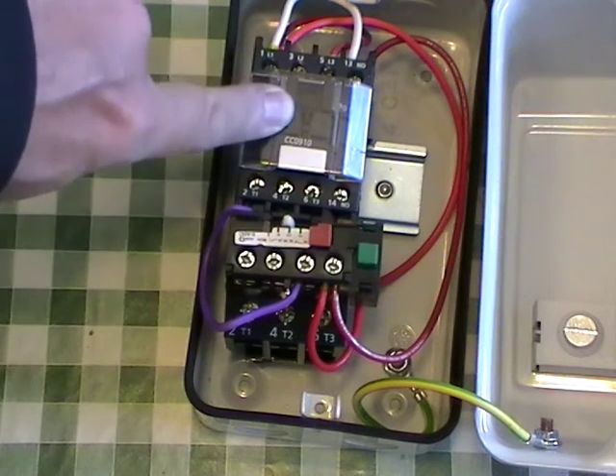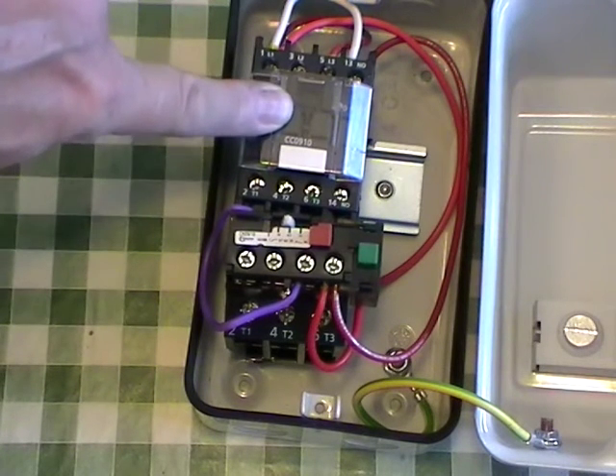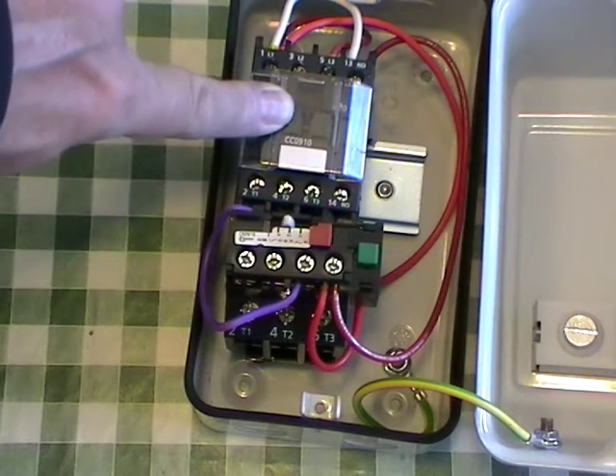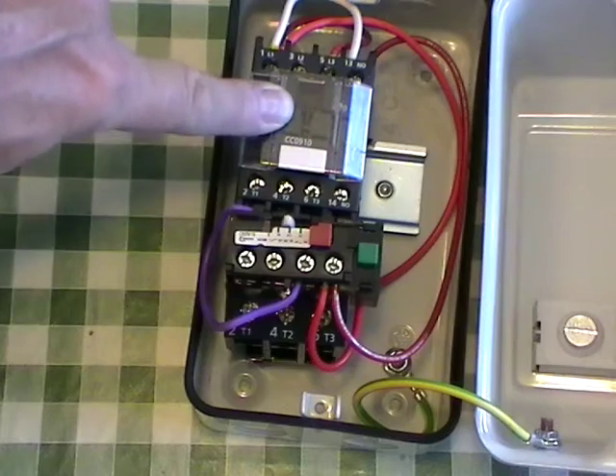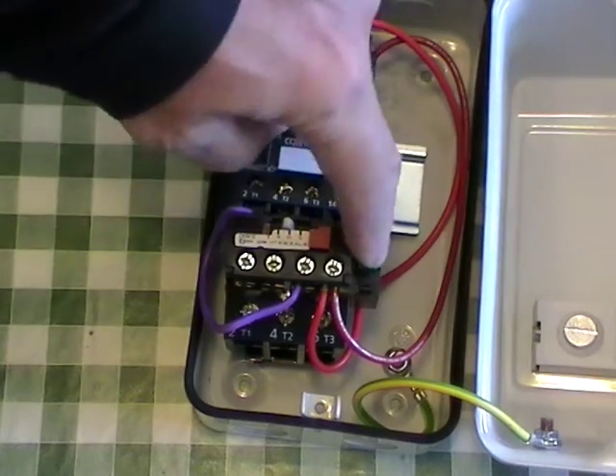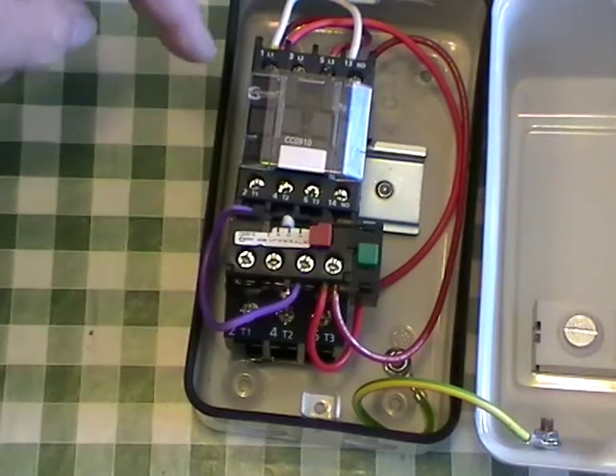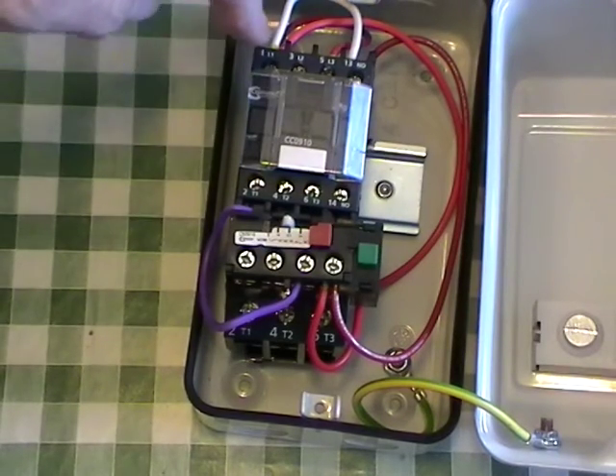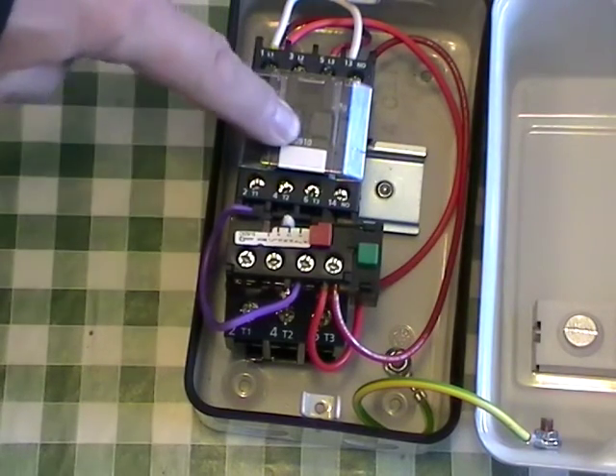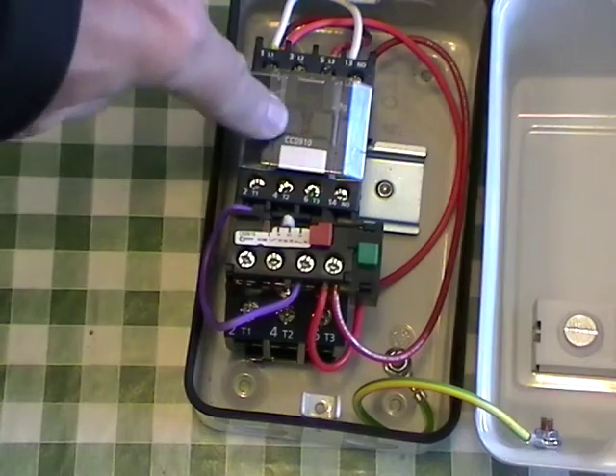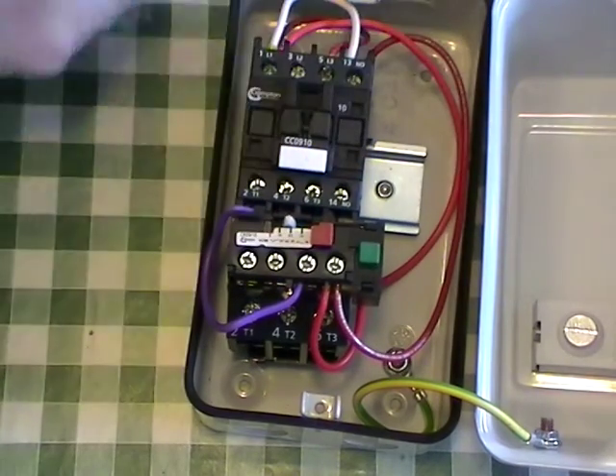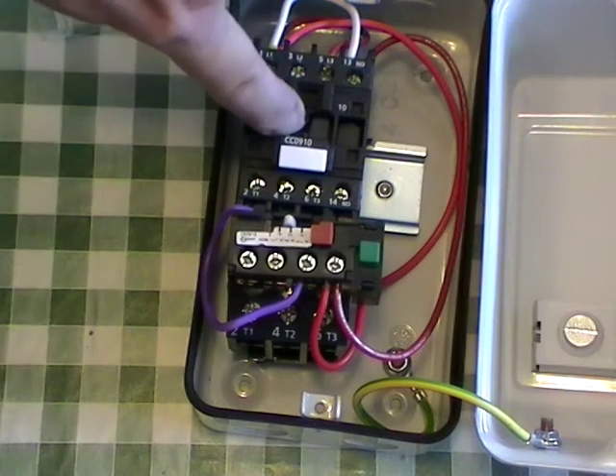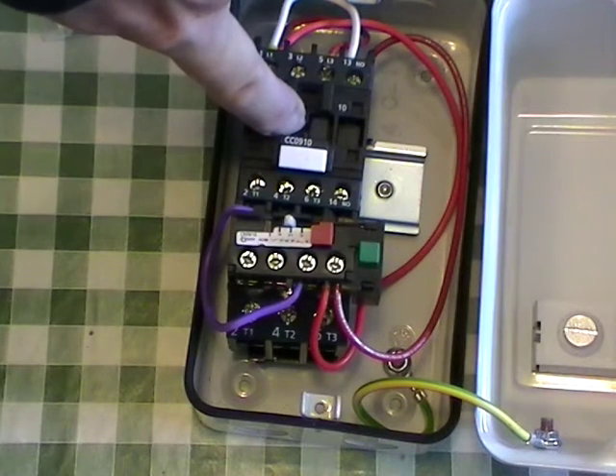Normally the contactor is not energized, is not switched on until the green button is pressed. The green button has 2 wires going to it which basically feed power to the coil to pull that unit down there. Pulls that down, and that makes contact to turn the motor on.